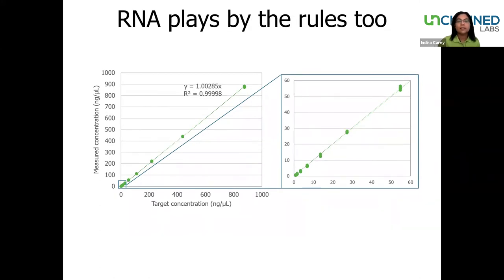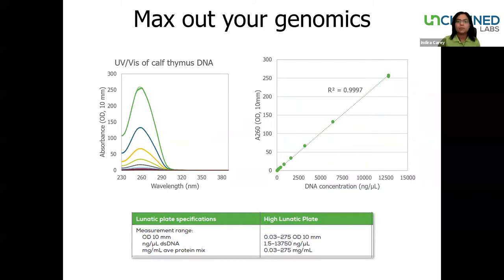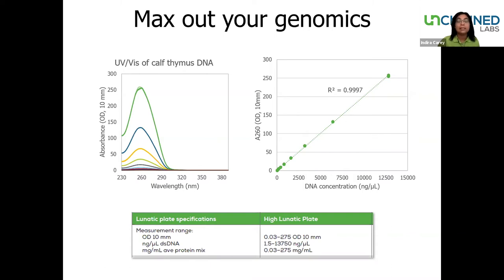We also see similar accuracy and reproducibility with a calf liver RNA dilution series — note again the same great results at lower RNA concentrations. Groups producing plasmids, for example, are typically working with high concentrations. I spoke with a customer recently who was getting variable results due to sample dilutions required with their own method, and for that group, Lunatic was a great solution because they could read high-concentration samples without dilution. The highest concentration of DNA in this dilution series was 12.8 micrograms per microliter, and you can see the nice R-squared value showcasing the high correlation.